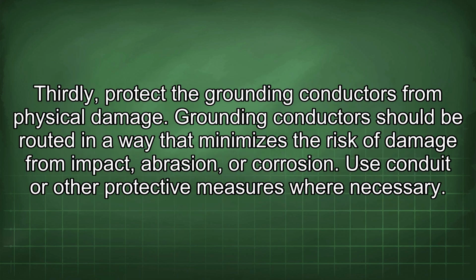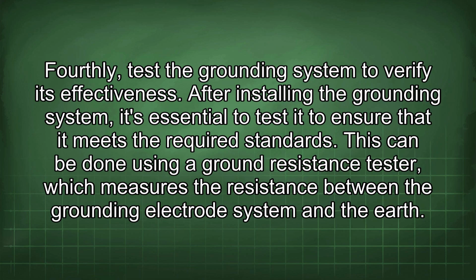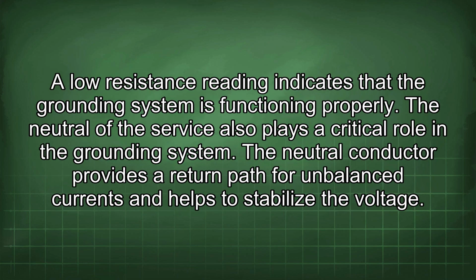Thirdly, protect the grounding conductors from physical damage. Grounding conductors should be routed in a way that minimizes the risk of damage from impact, abrasion, or corrosion. Use conduit or other protective measures when necessary. Fourthly, test the grounding system to verify its effectiveness. After installing the grounding system, it's essential to test it to ensure that it meets the required standards. This can be done using a ground resistance tester, which measures the resistance between the grounding electrode system and the earth. A low resistance reading indicates that the grounding system is functioning properly.